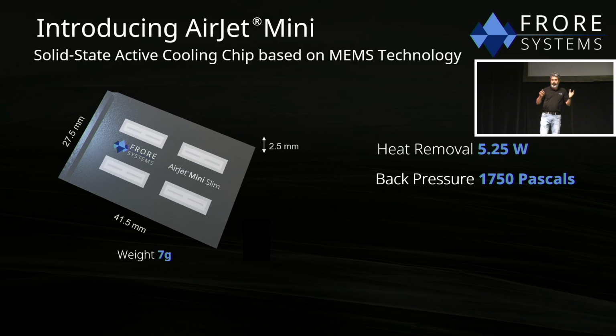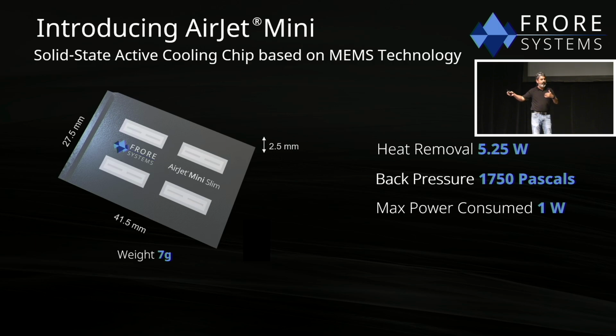If you compare it with fans, which would be at 150 to 200 pascals of static pressure head, this is almost 10 times higher. And this is important because that will drive how you can put this into very compact devices and still maintain performance. You won't lose performance because of the density of packaging; it'll handle the system resistance much, much better than a fan can. All right? It consumes 1 watt to remove the 5.25 watts.